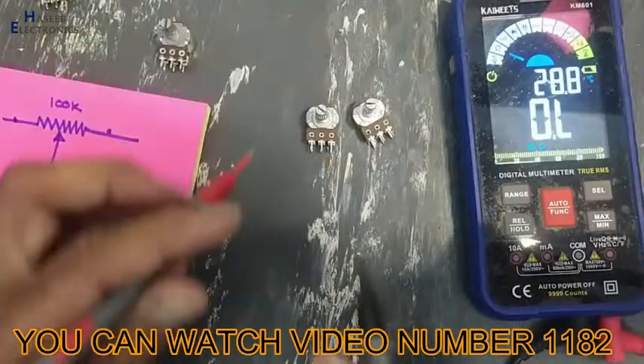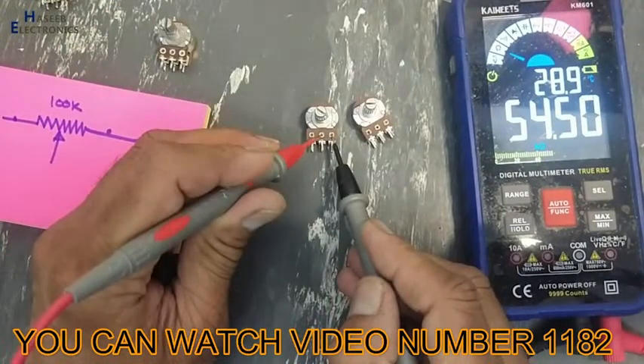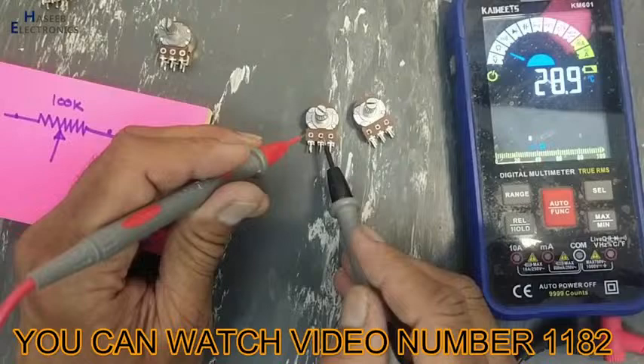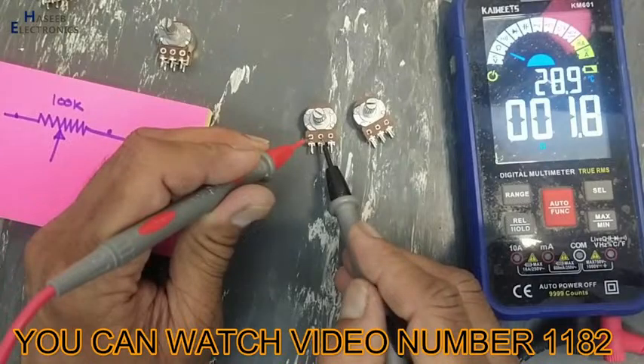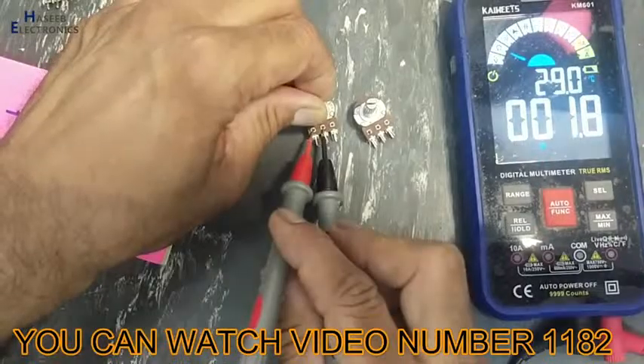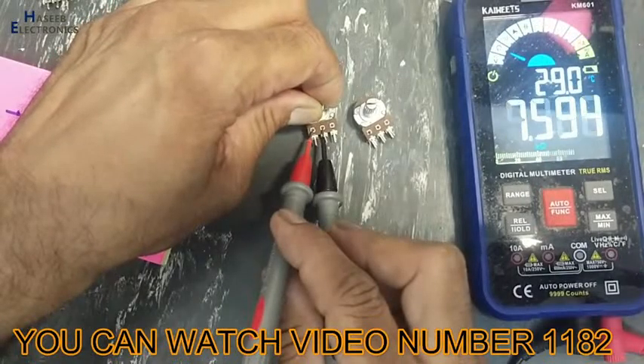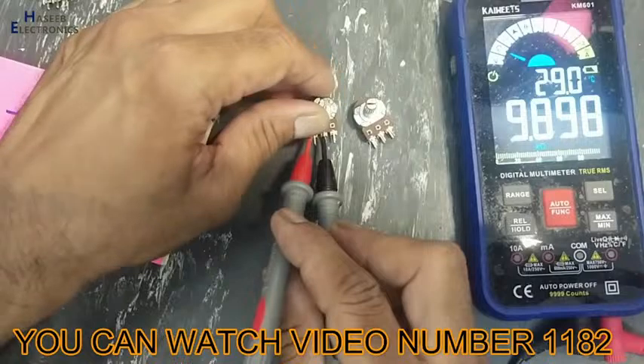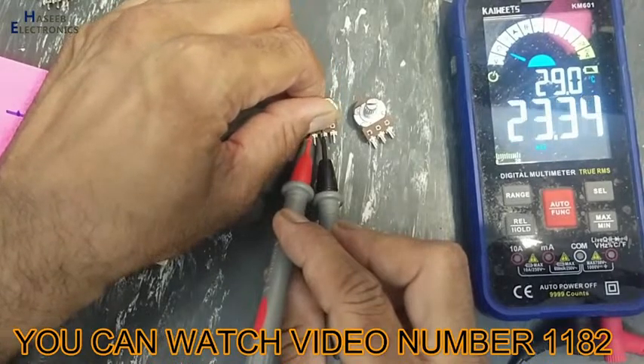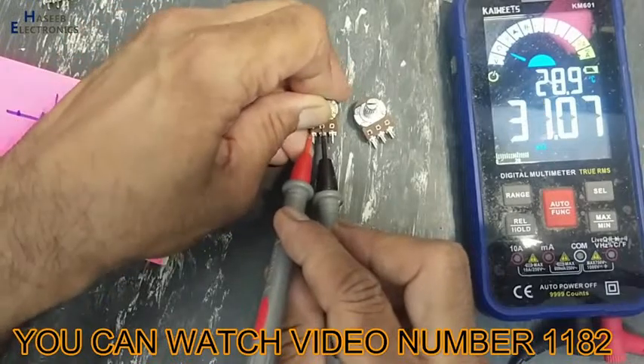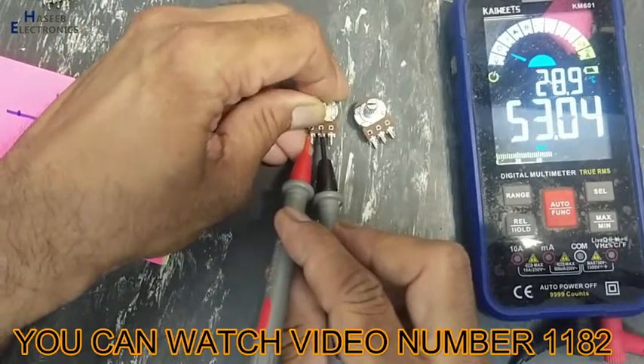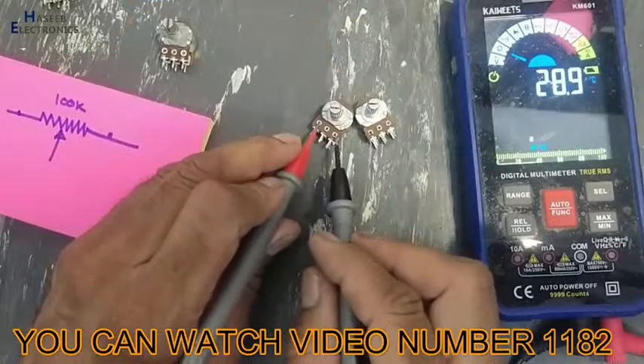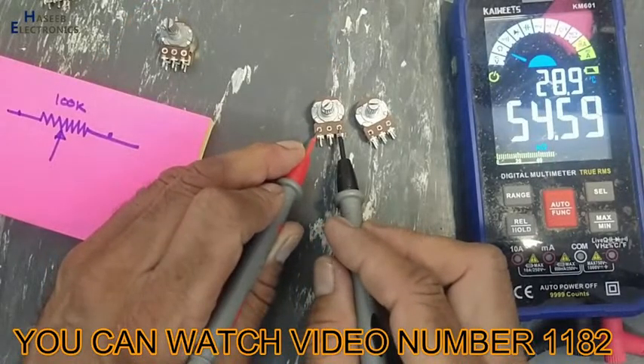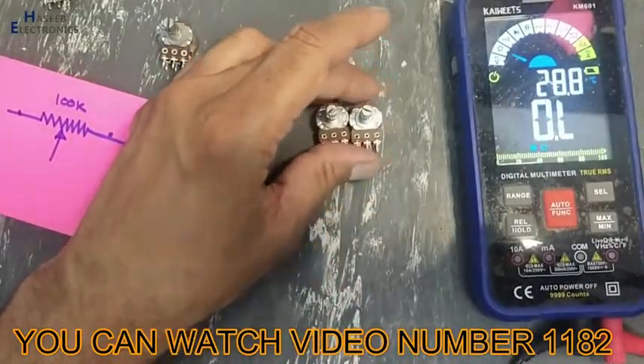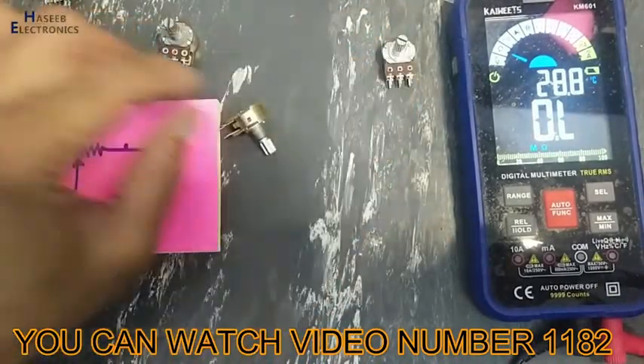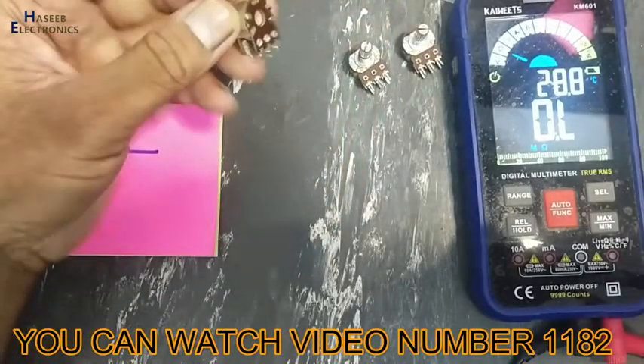When we purchase a new component, especially potentiometers, we must verify its resistance, whether the resistance is good or not. If we check its linearity, it is dividing linearly, so its linearity test is good, but its total value RT is wrong. So I will return these parts to the seller and purchase new 100K potentiometers.